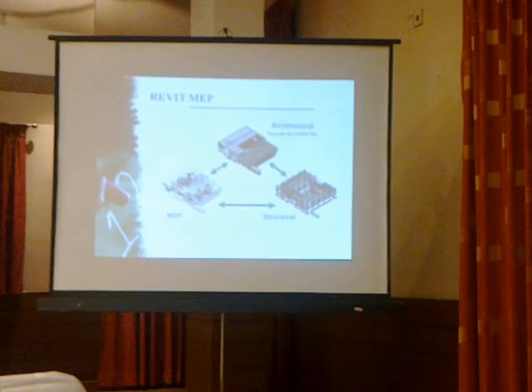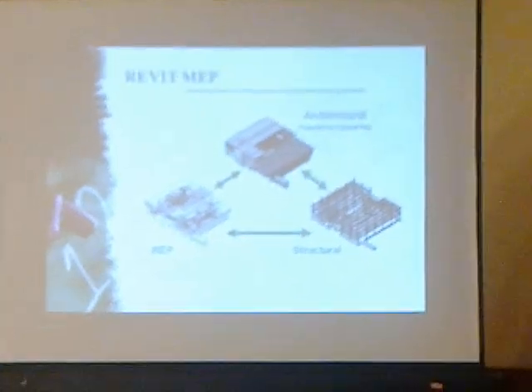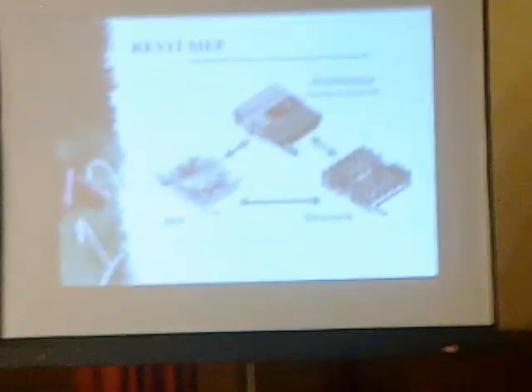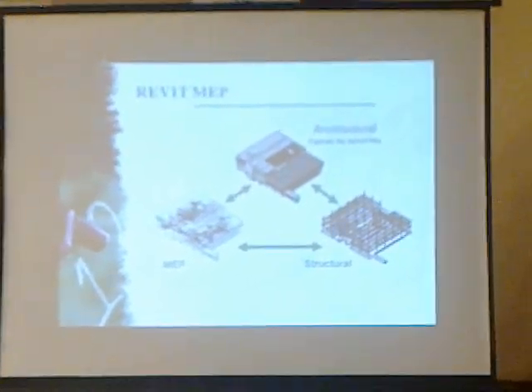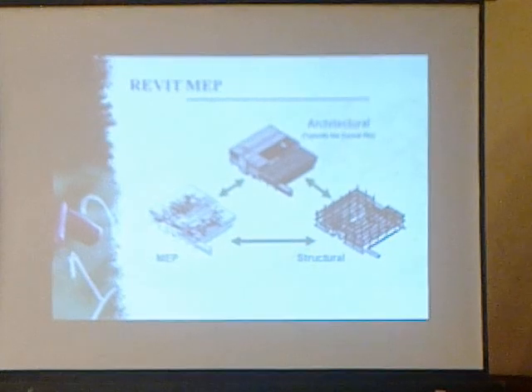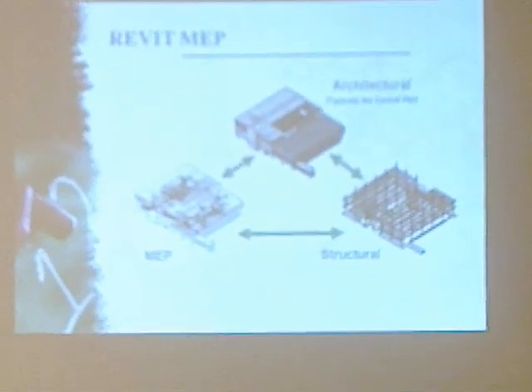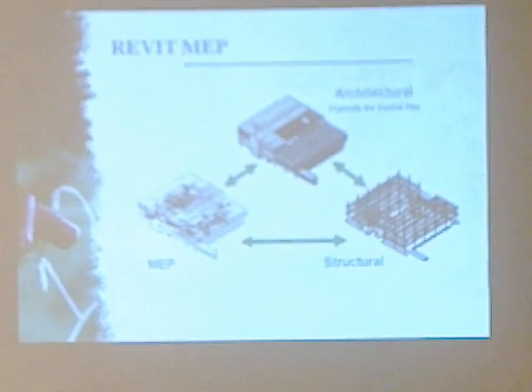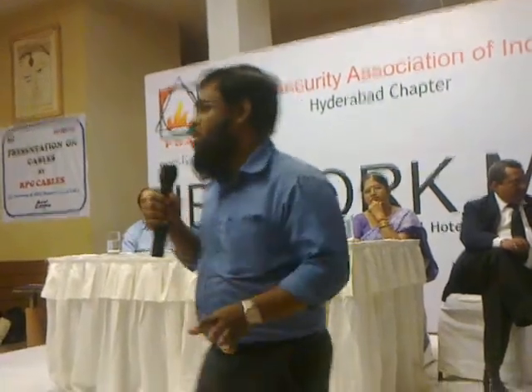If you compare CAD with Revit: in CAD you can only go for drafting, but in Revit you can go for designing. In CAD, different services are drafted in different files, but in Revit everything is done in a centrally located file. For example, if a duct is running at the bottom of 9 feet and the electrical team tries to use that clearance, Revit MEP will immediately stop that or give an error message — the electrical people can't use that space. So from a coordination point of view, Revit gives you excellent capabilities.